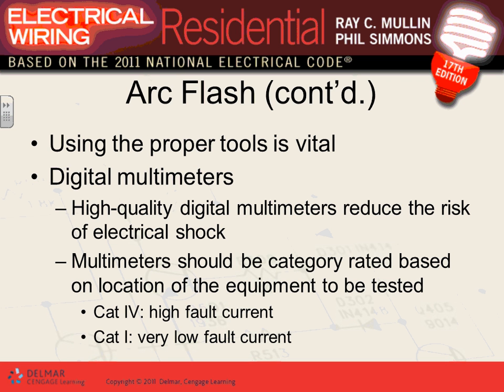The whole idea, guys, is that if you're using the meter and there's a short circuit right into it, there are stories—if you go online, on the Fluke website—of people dying because the meter exploded while they were taking a measurement, because the meter wasn't rated to handle the short circuit.